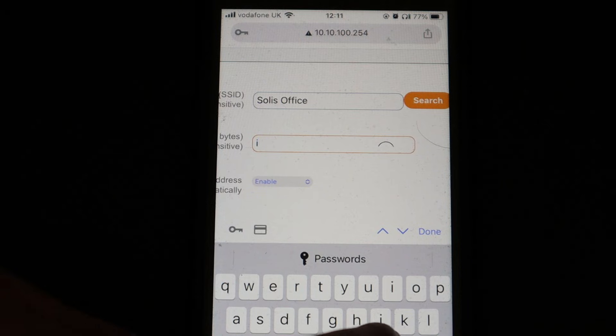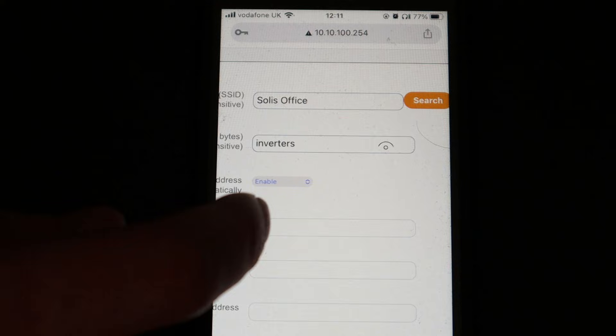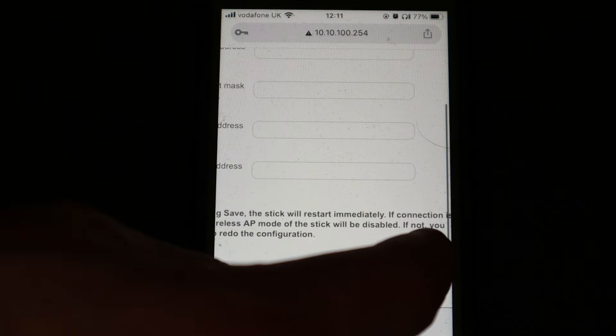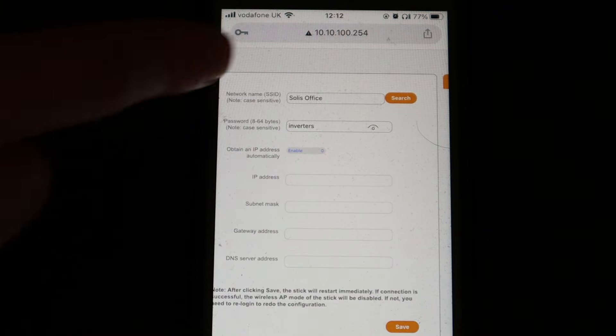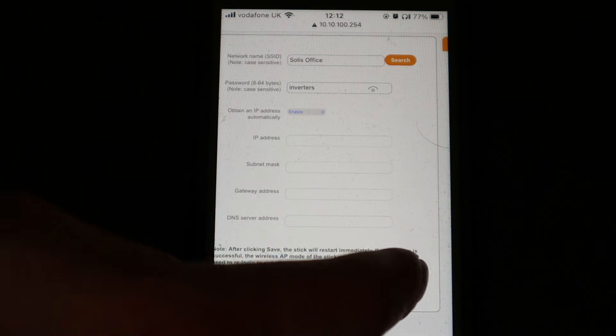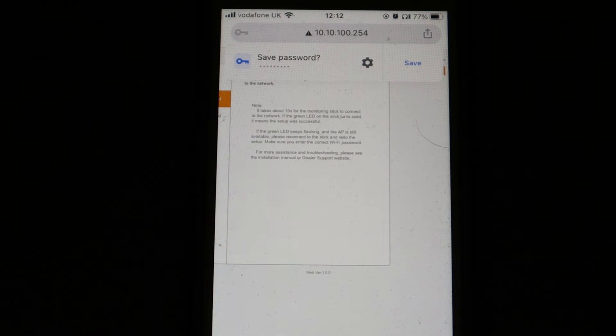Select the customer's network and press OK. Then in the next field, type in the password for that network. It's very important that you get this password right — any typos won't be revealed at this stage and you'd just have to try again. You can also choose to obtain an IP address automatically, which in most cases you'll want to leave enabled, or you can disable it and set a static IP. Then press Save and wait ten seconds for the data logger to connect to the internet, and thereafter to SolisCloud.